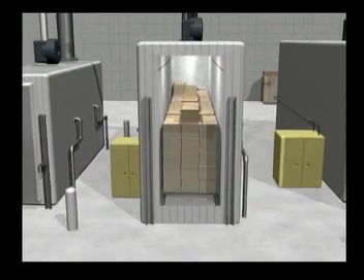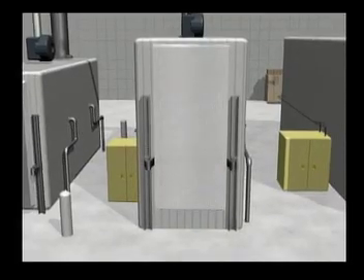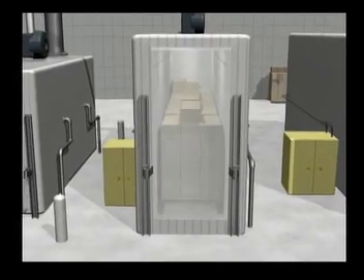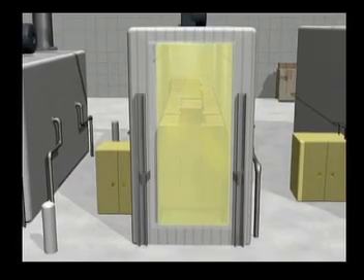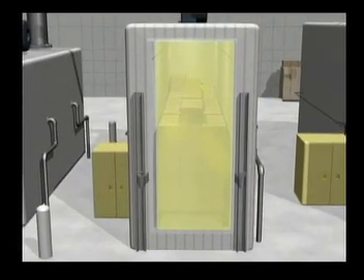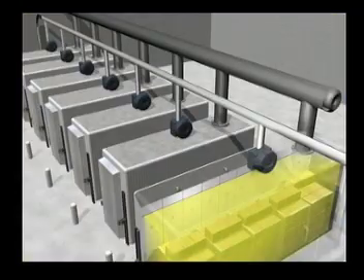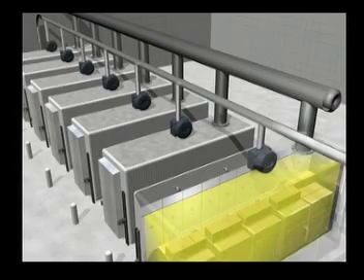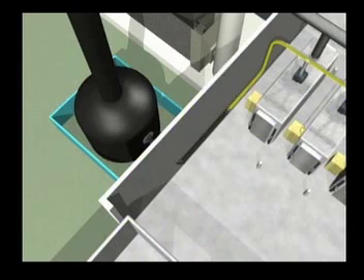Packaged medical products are added to the chamber and the doors are sealed. The chamber is then filled with ethylene oxide, which penetrates the packaging over several hours, killing any germs and sterilizing the products inside. After the sterilization phase, ethylene oxide is removed from the chamber in several steps. First, about half the gas is pumped from the chamber to a pollution control device called a scrubber, where it is removed by chemicals.